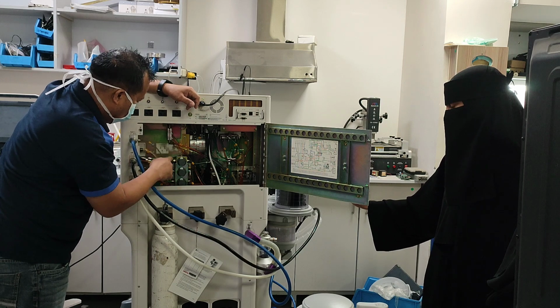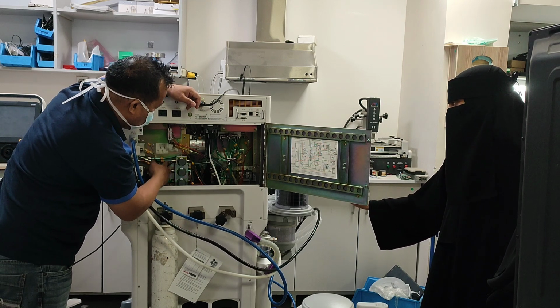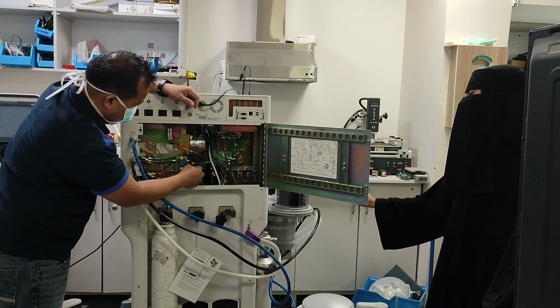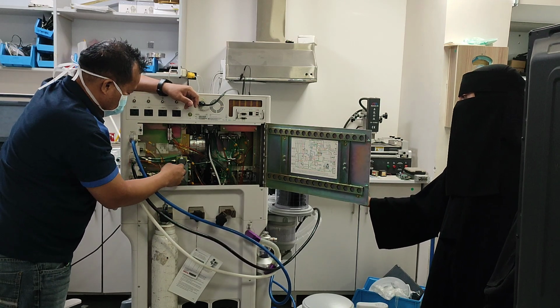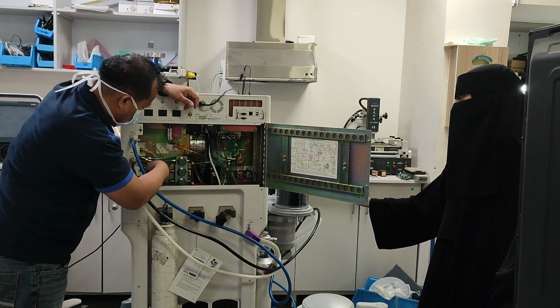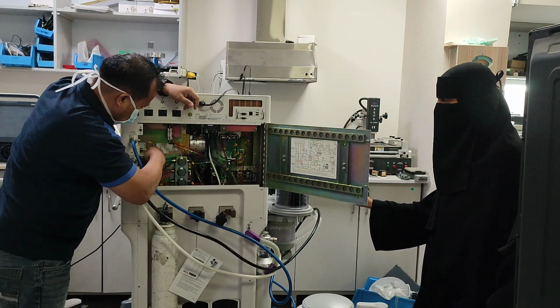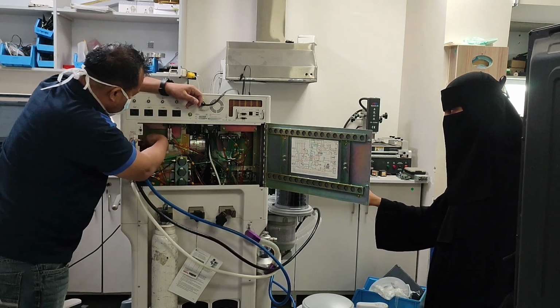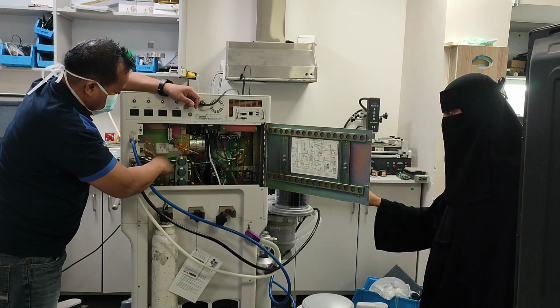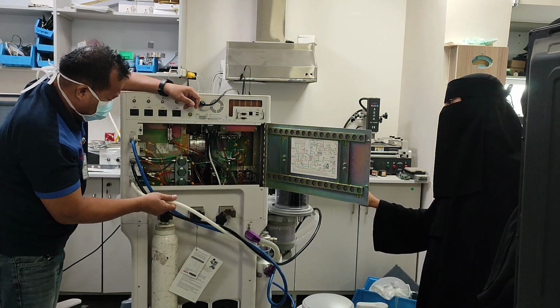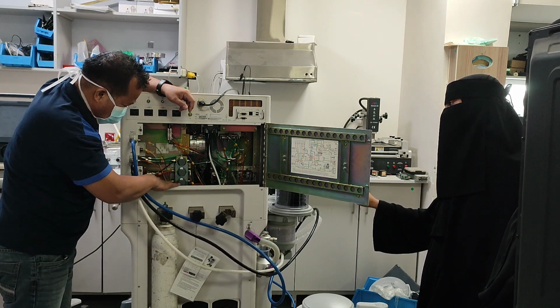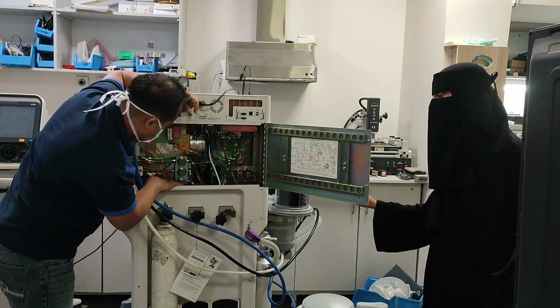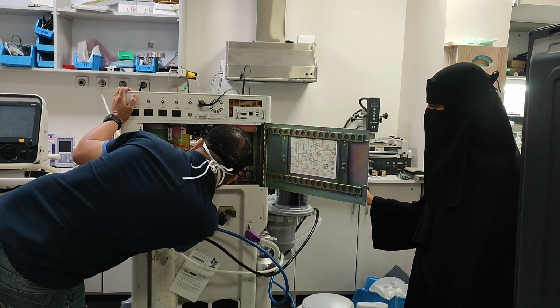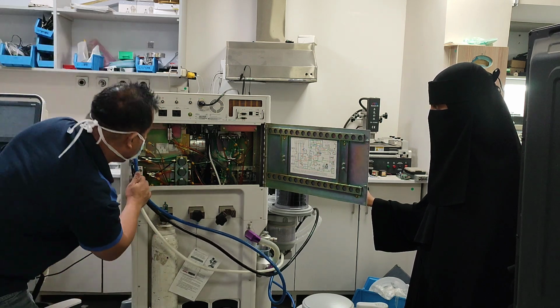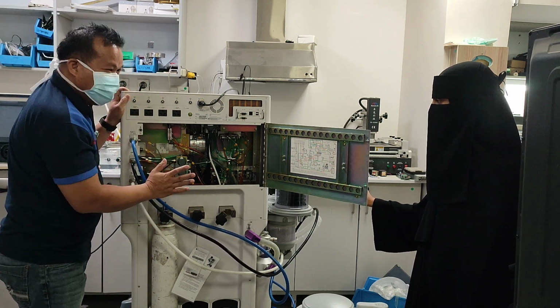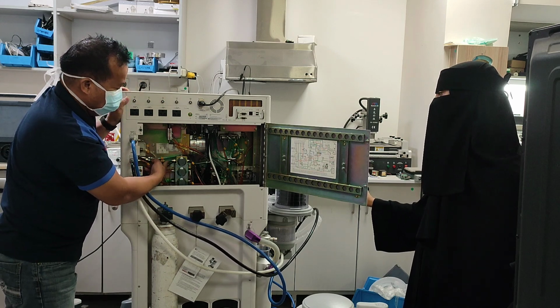If you see, the nitrous oxide and the O2 are the same color here, but it's very dangerous to interchange them. The orange one is the air. See, the air is coming here, orange. And the nitrous also goes to this one here. And the oxygen is white, but the color here is also the same, light green. No, that's just reflection only. So the blue is a light blue color. This is not the same color. This is green and this is the light blue.